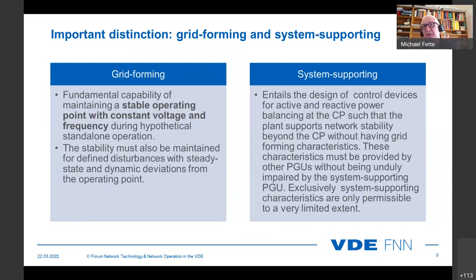And system supporting entails the design of control devices for active and reactive power balancing at the connection point, such that the plant supports network stability beyond the connection point without having grid forming characteristics. These characteristics must be provided by other PGUs without being unduly impaired by the system supporting PGU. Exclusively, system supporting characteristics are only permissible to a very limited extent. It simply says the one grid forming.